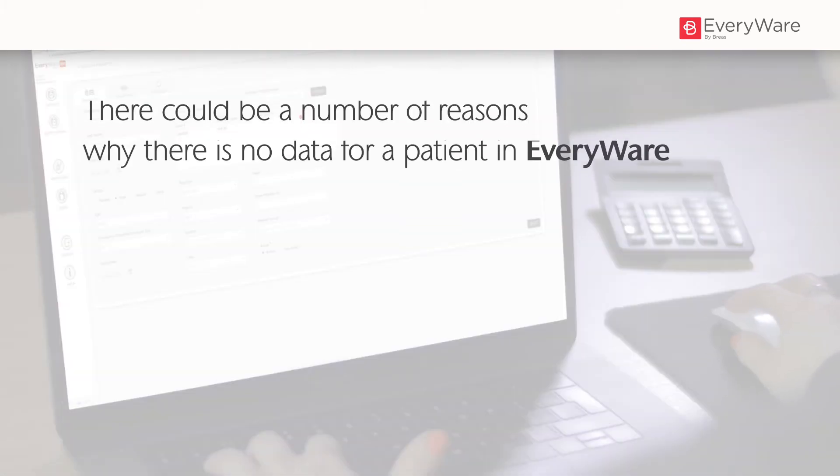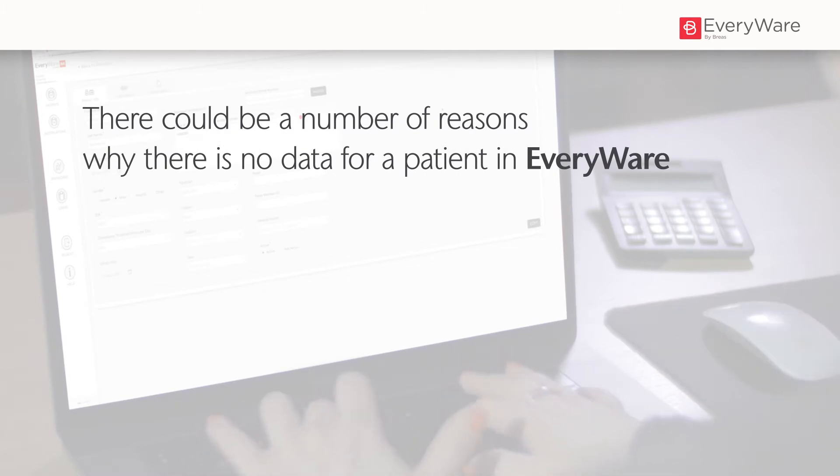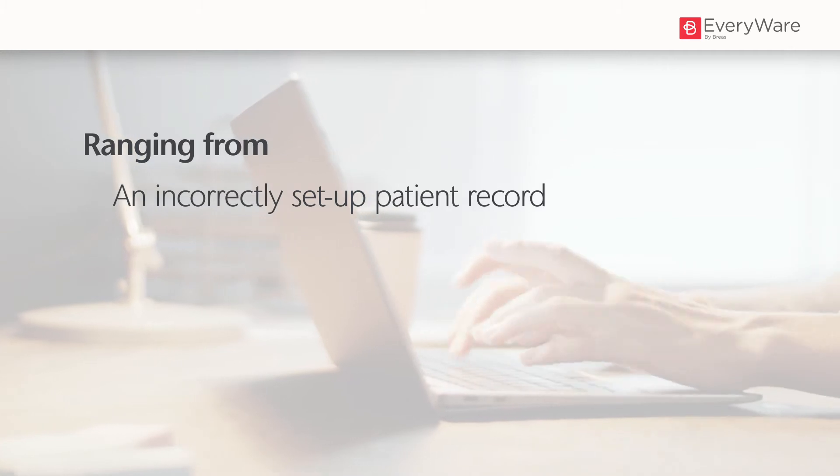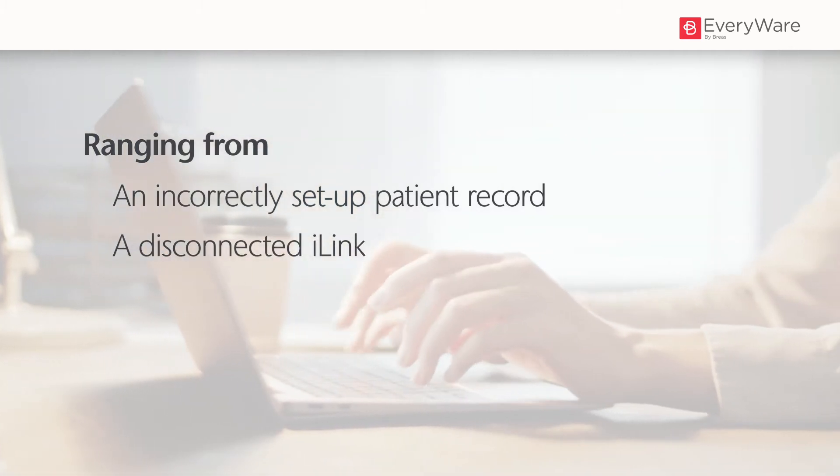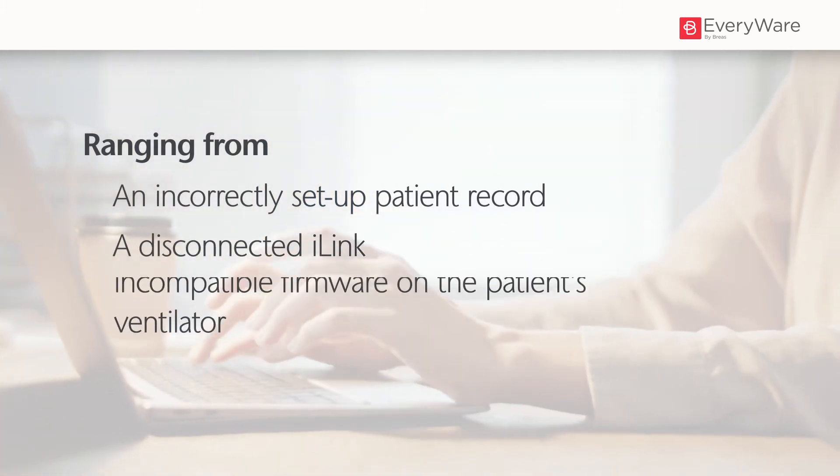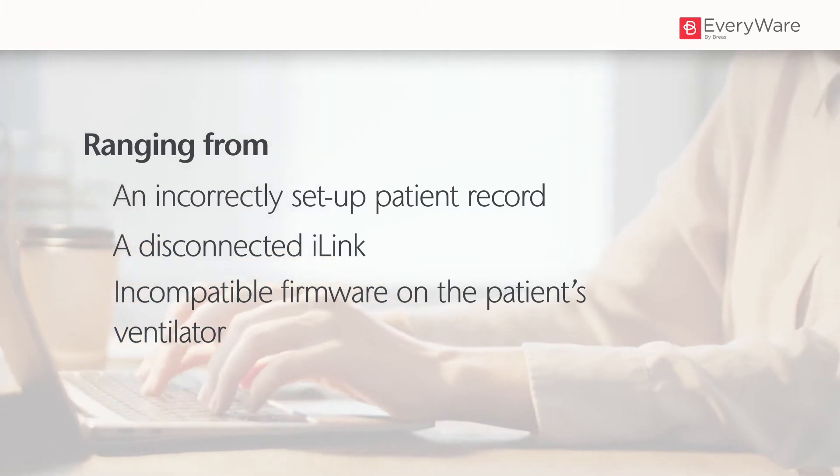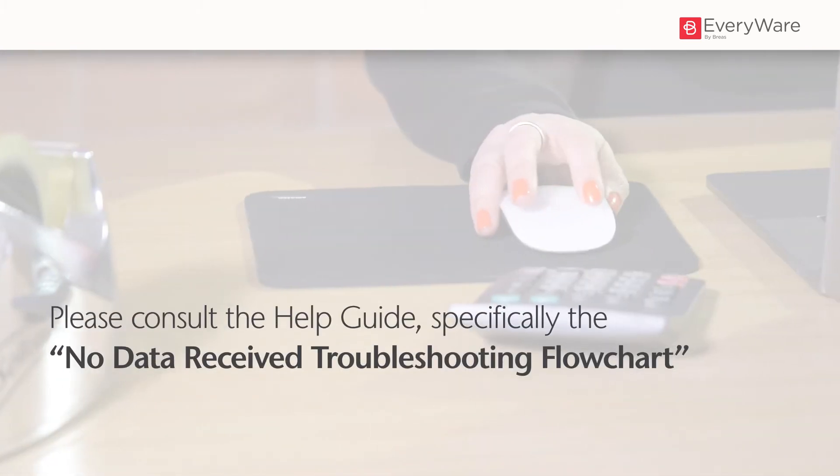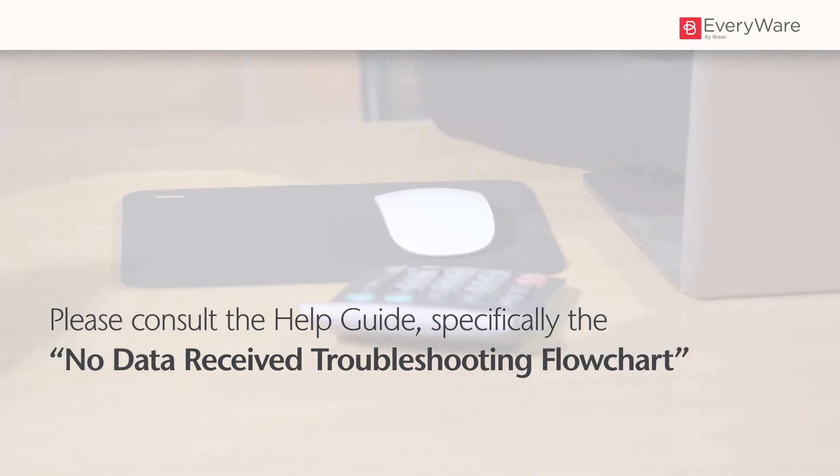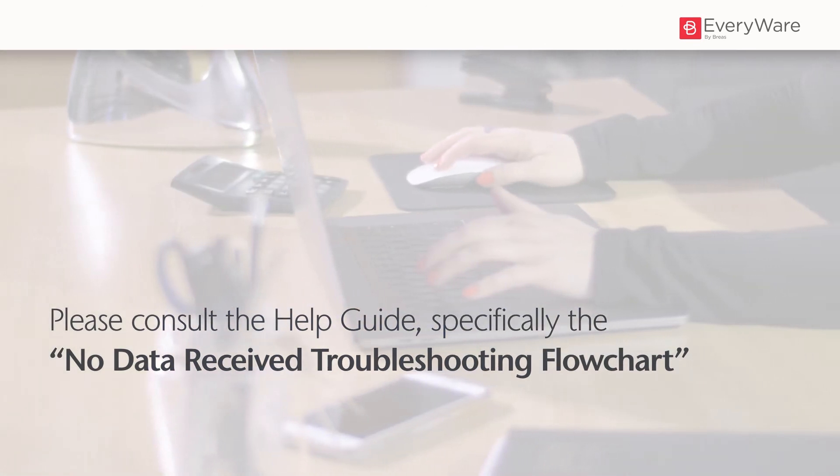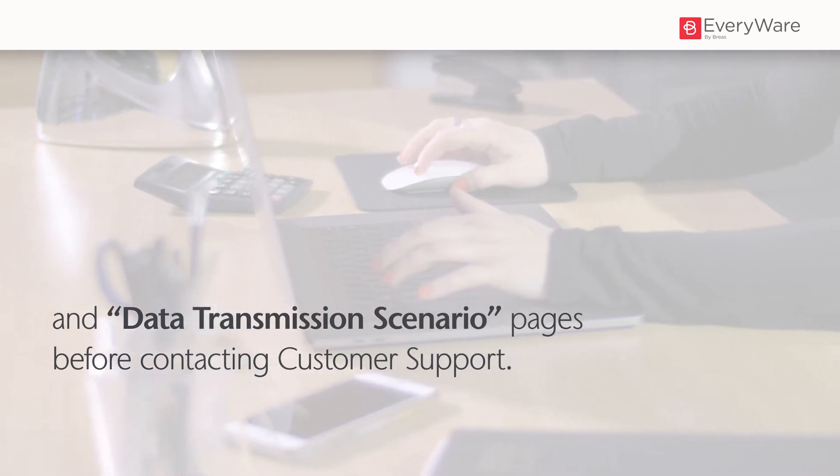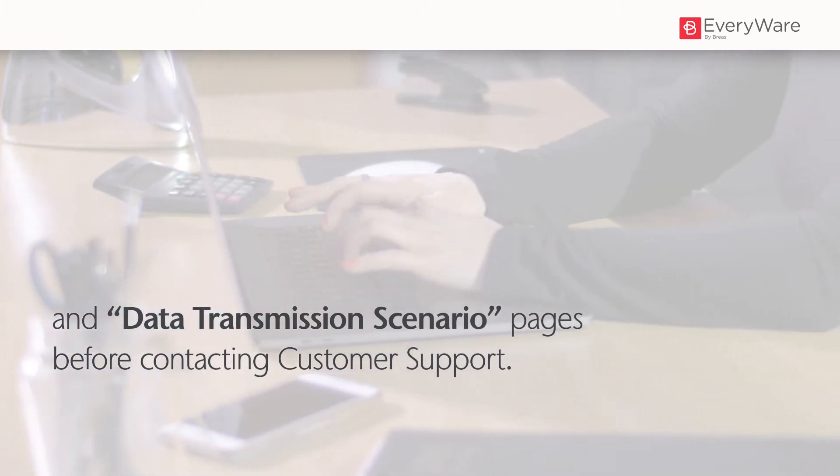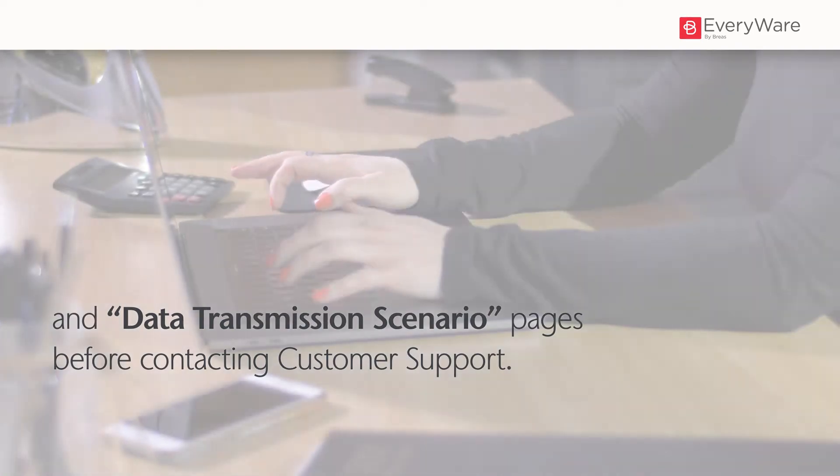There could be a number of reasons why there is no data for a patient in EveryWare, ranging from an incorrectly set up patient record, a disconnected i-link, to incompatible firmware on the patient's ventilator. Please consult the help guide, specifically the No Data Received Troubleshooting Flowchart and Data Transmission Scenario pages before contacting customer support.